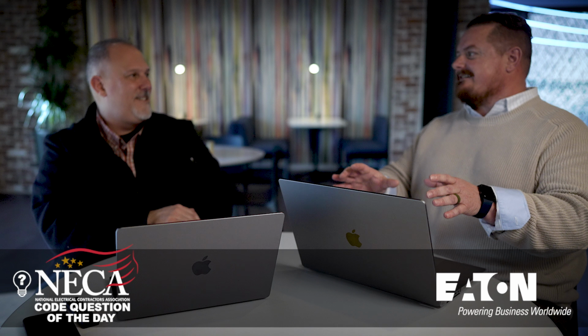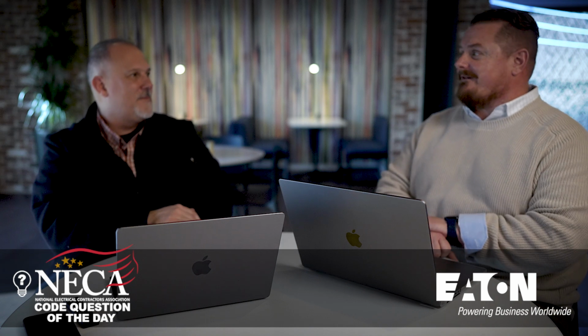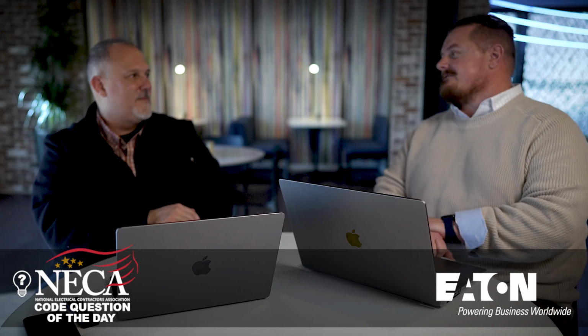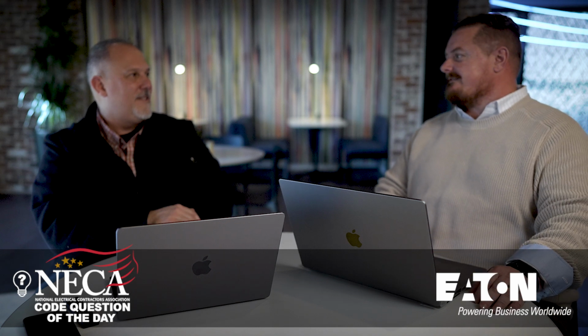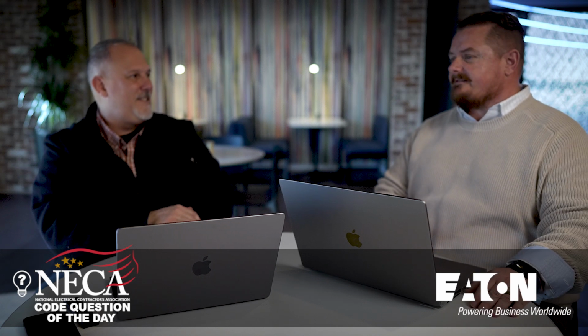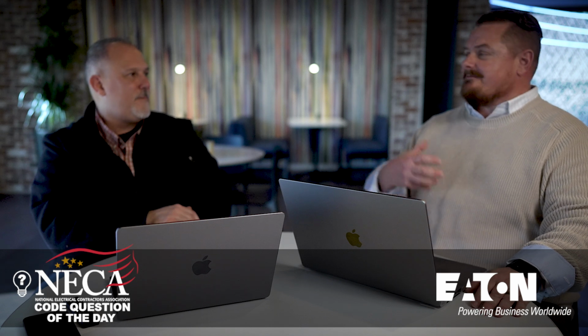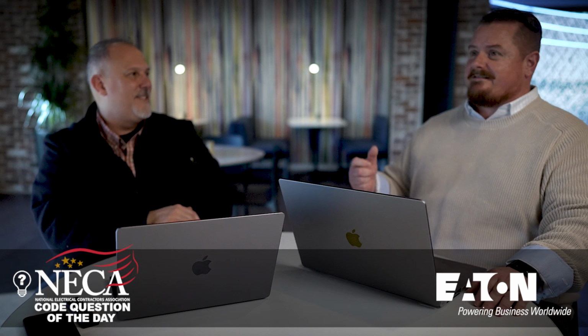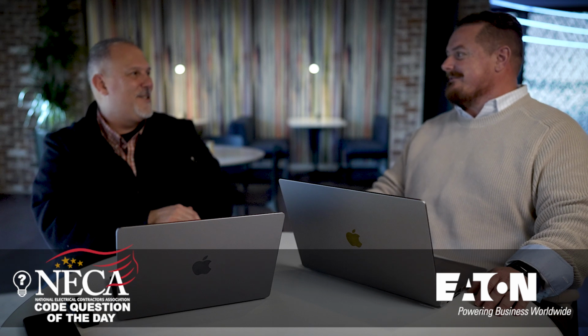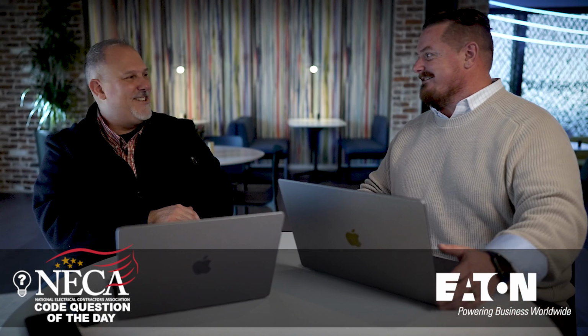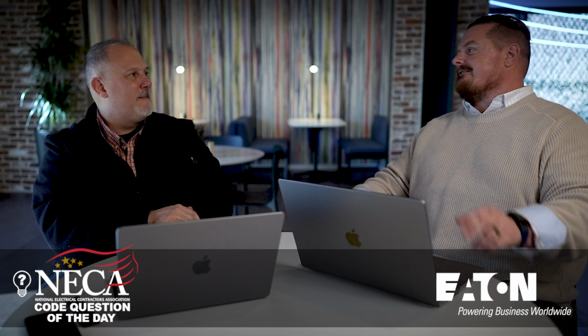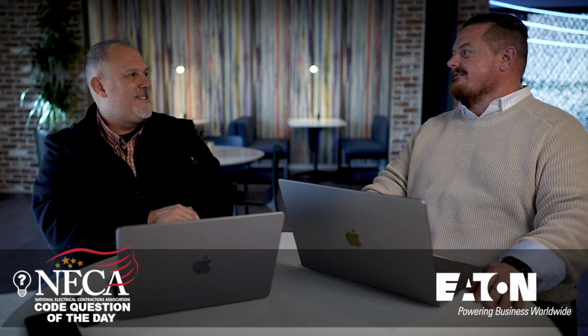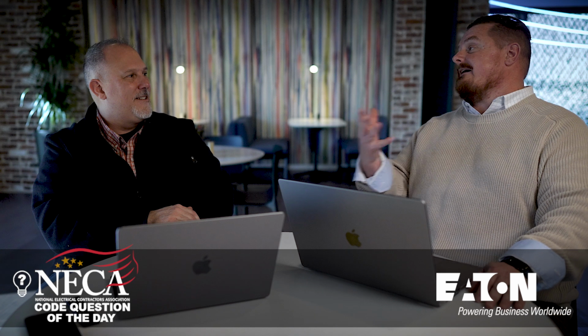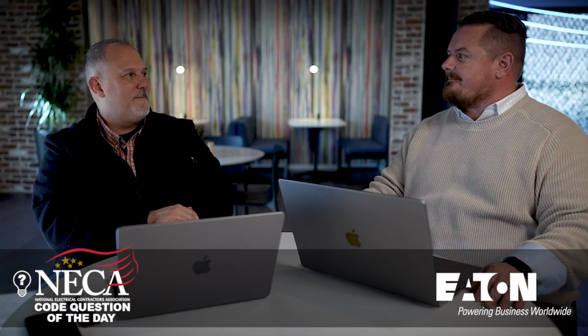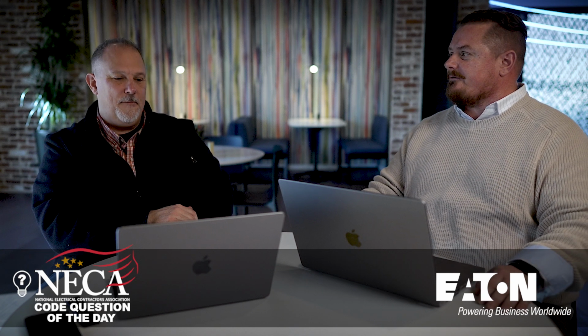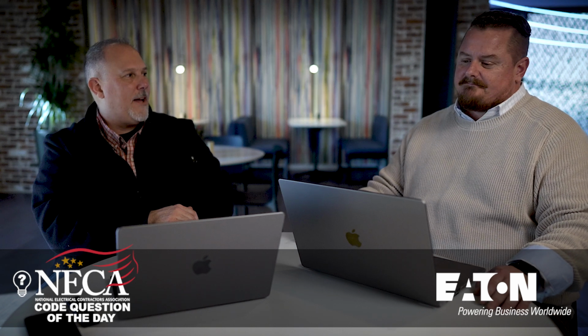Yeah. And they're very territorial of their elevator control area. So for an electrician to get in there or an electrical inspector to get in there and verify that stuff, you're pretty much taking the elevator inspector's word for it and the electrical contractor's word for it at that point, because it's hard. There are times where I couldn't even get in there to verify that the GFCI that was installed for the sump in the elevator pit was correct. Yeah. And the elevator inspector says, nope, that's our territory. We'll verify it. We'll make sure it's done. Wow. So yeah, that's my thought process as to why that's something that might not be commonly enforced or occurring. I agree with you 100%.